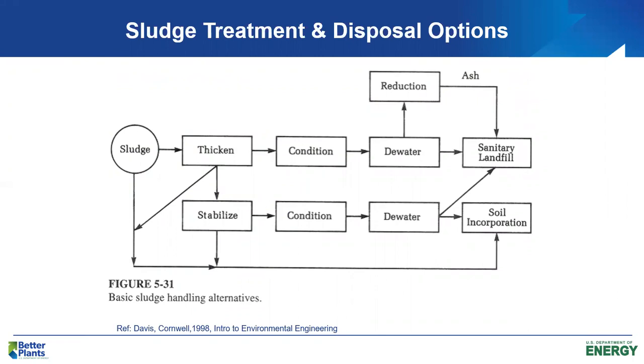When we operate an activated sludge wastewater treatment plant, we may generate primary sludge and secondary sludge that have to be treated. Or we have quite a few activated sludge processes that do not use primary settling, so all we have to deal with is the waste-activated sludge. There are quite a few options for what to do with the sludge — mostly having to do with reducing water content through thickening, dewatering, chemical conditioning, or even burning the sludge to produce material that's mostly ash and low in water content.